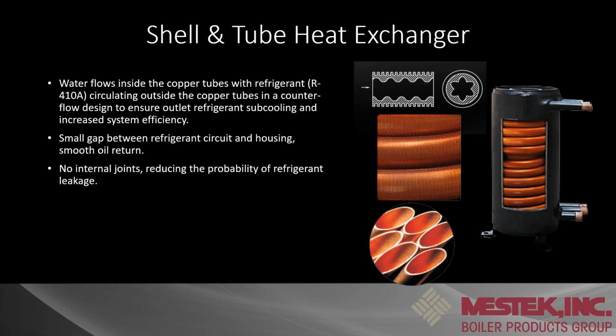So a shell and tube heat exchanger is basically like a flooded evaporator coil. This is where your phase change happens with the refrigerant. To explain it a little better, you have these copper tubes coiled up here. Inside the copper is where your water runs. Outside the copper is where your phase change happens. So we're flooding that evaporator coil and flashing off, making our energy transfer from refrigerant to water through this coil.